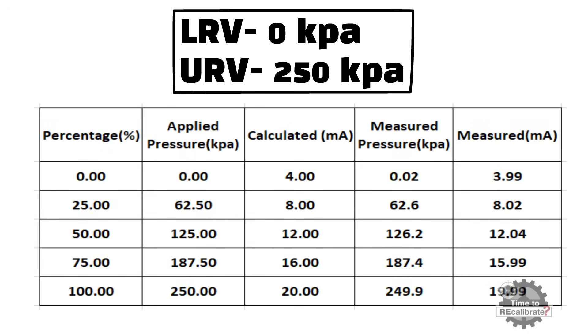Now divide 250 into 4 equal parts. For example, 25% of 250 kPa is 62.50 kPa. So put this value in the applied pressure column just beside 25%. Calculate the same value for 50% and 75% of 250 and put these values in the applied pressure column. Put the 4 to 20 milliampere analog output standard values in the calculated milliampere column. For example, when there is 0% input, the calculated analog output value is 4 milliampere. Write down this value in the calculated milliampere column.